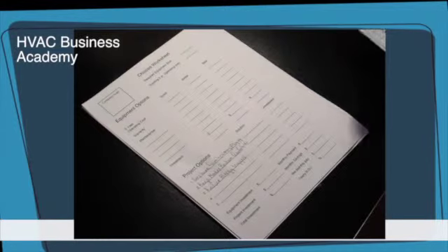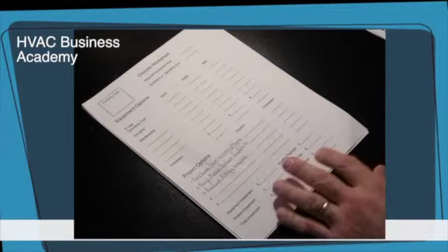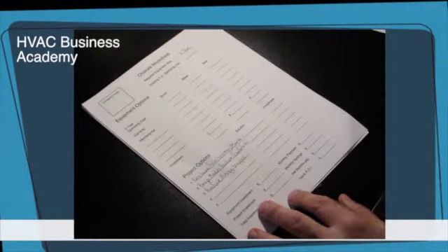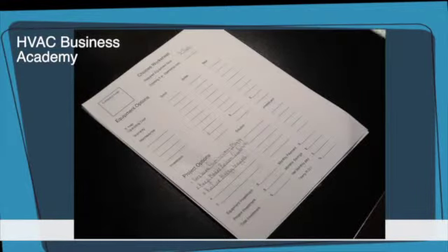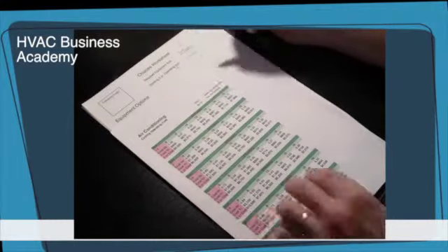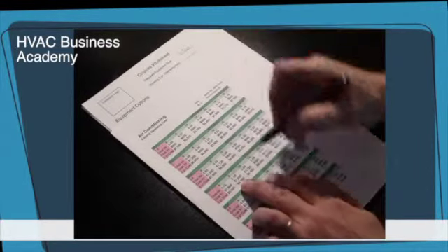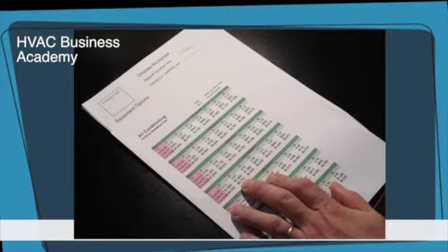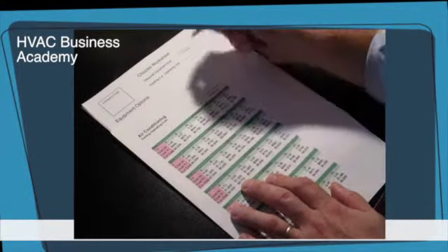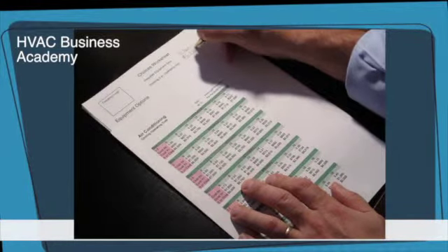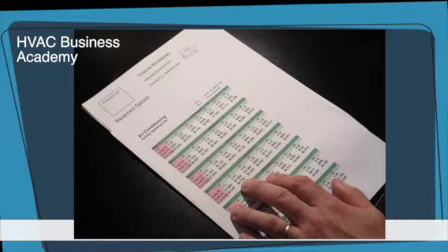Alright, see here, my heating and cooling load calculation says that we need a 3-ton air conditioning system. And the existing system, operating cost over 5 years, so we can compare that to the new ones. We have a 3-ton, it's operating at about an 8 SEER. So the existing system is costing $6,750 to operate over 5 years. That's quite a bit.